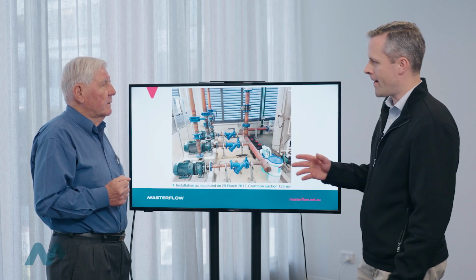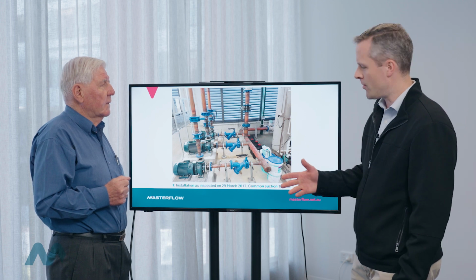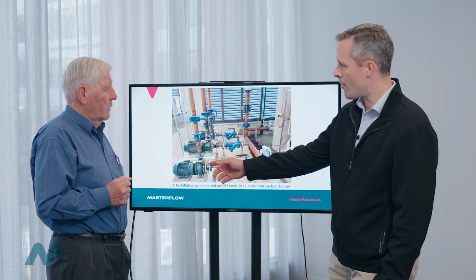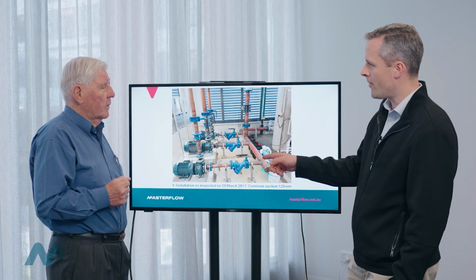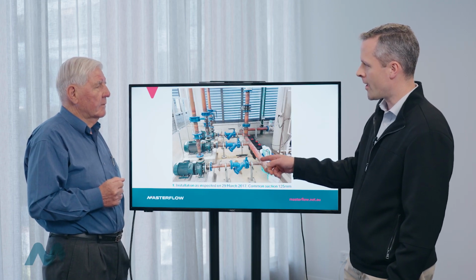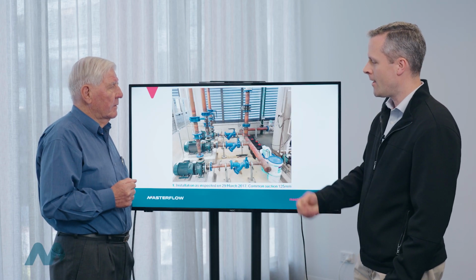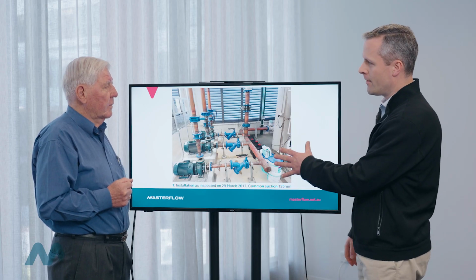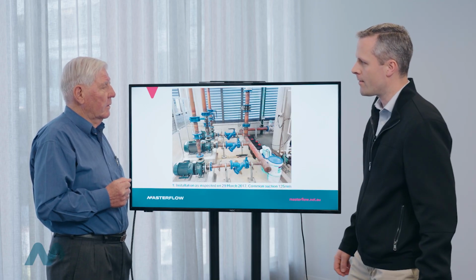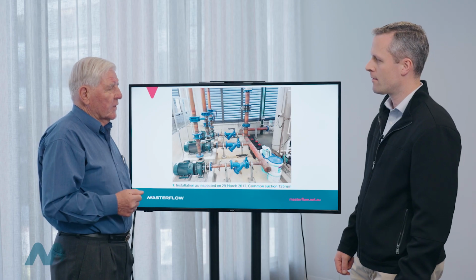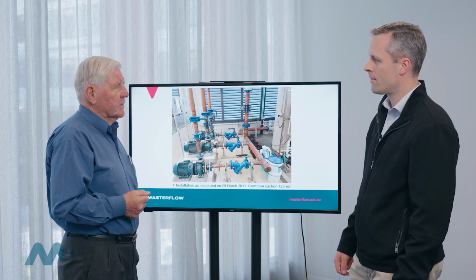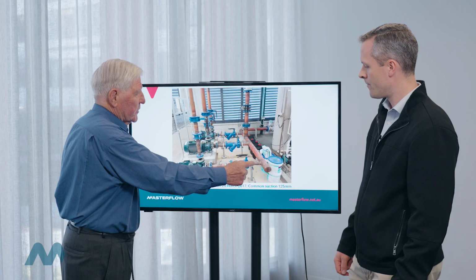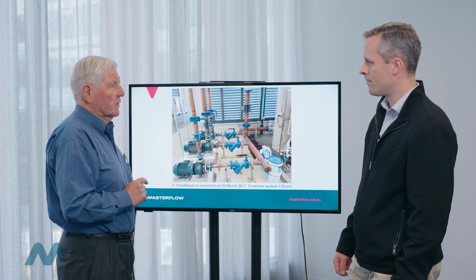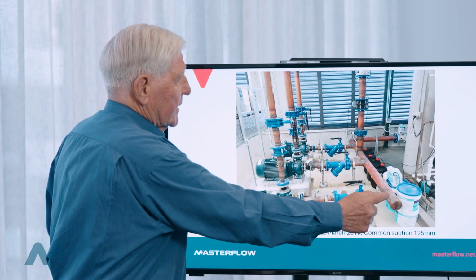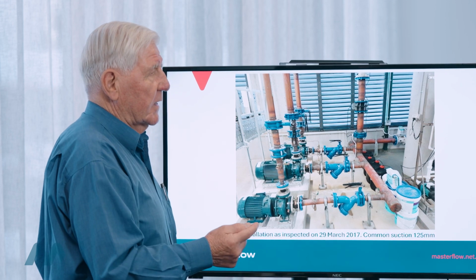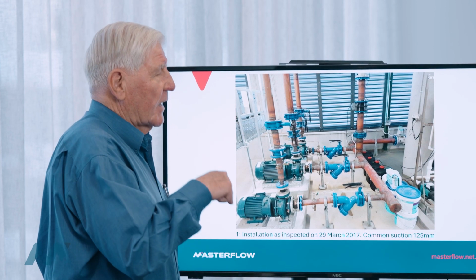So tell me, you talk about evacuating air. From my experience on the tools, I've found that when the pumps are operational, if you were to open a valve on the suction side, you can actually draw air in, especially if the pressure available is very close to the pressure required of the pump. Well, the only thing that's important whether air comes in or goes out is what is the pressure differential across that ball valve. If the pressure in this suction pipe is higher than atmosphere, air will come out, and if it's lower, air will go in.